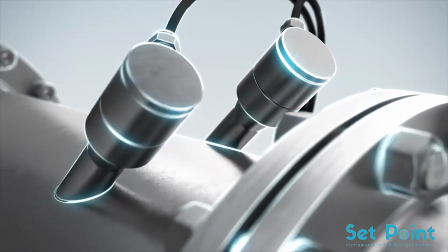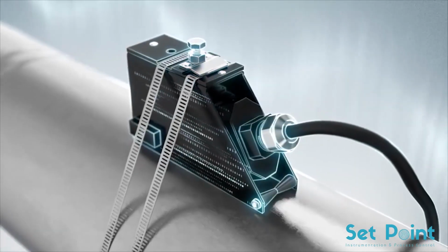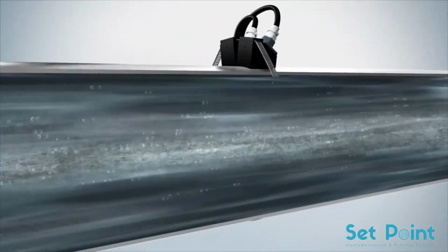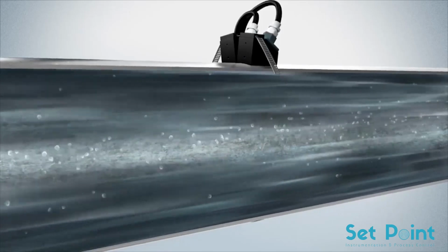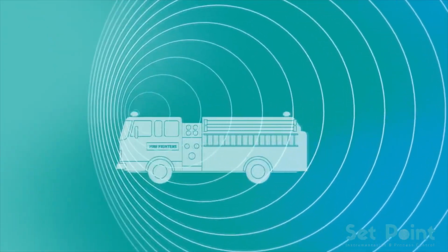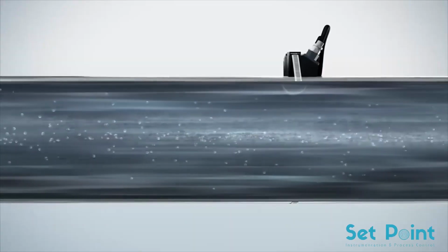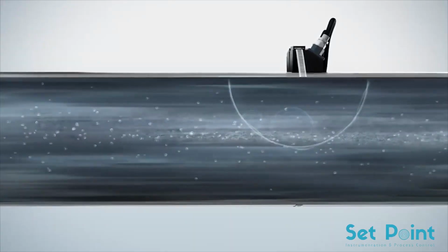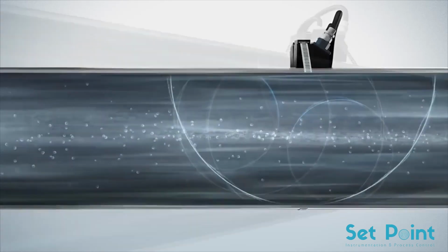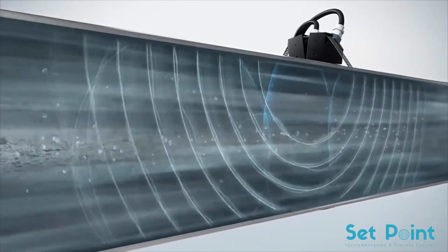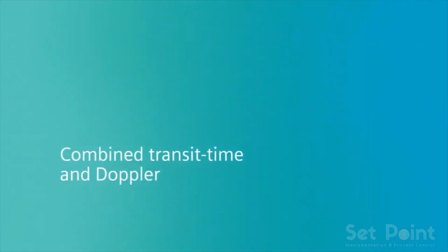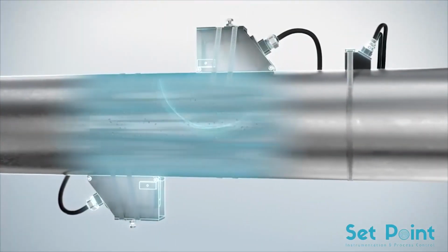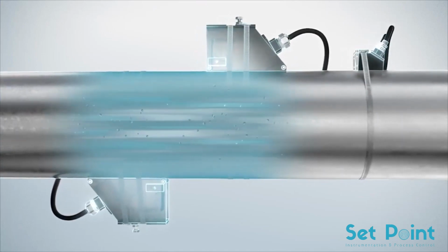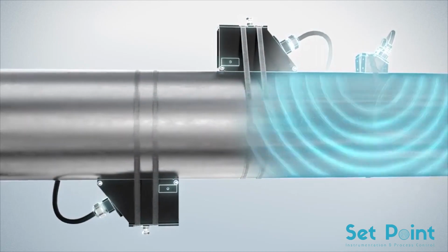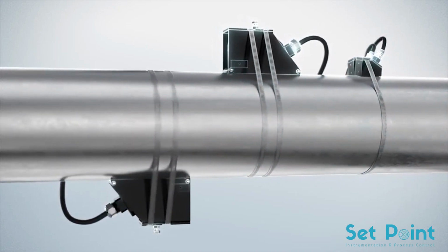As the flow meters have no parts that wear, measurements remain constant and the total cost of ownership is low. If the medium contains dispersed particles or bubbles, Siemens uses a method based on the Doppler effect, a frequency shift similar to a passing fire engine. When an ultrasound wave hits the particles, the sound waves are reflected and the wavelength shifts based on the particle's speed. The faster their speed, the greater the frequency shift. To guarantee maximum measuring accuracy, even if the state of the medium changes, Siemens has developed a combined transit time and Doppler mode method, enabling automatic switching.